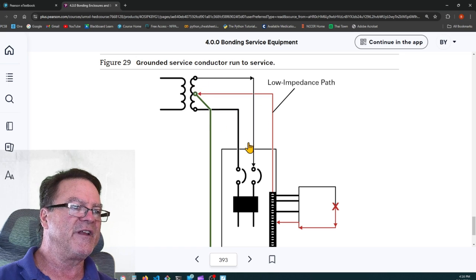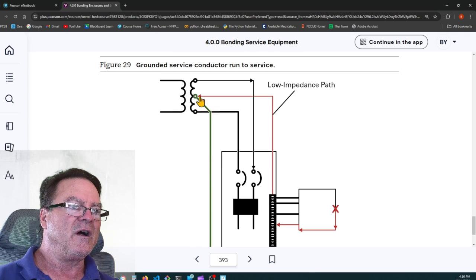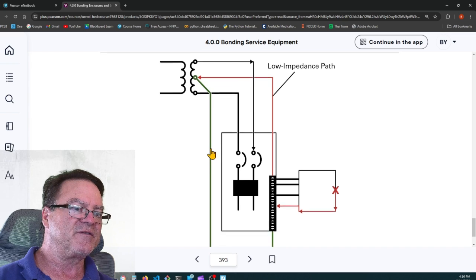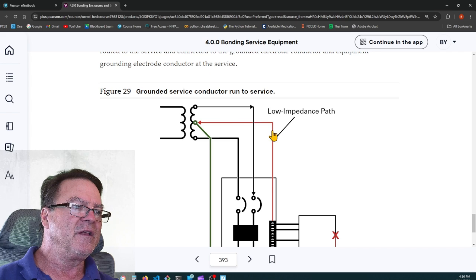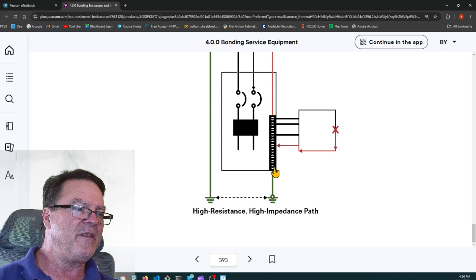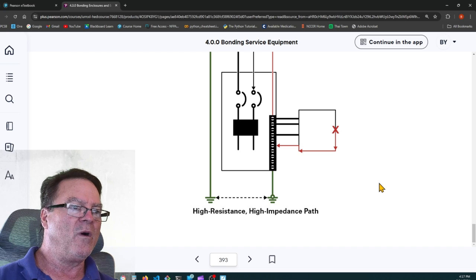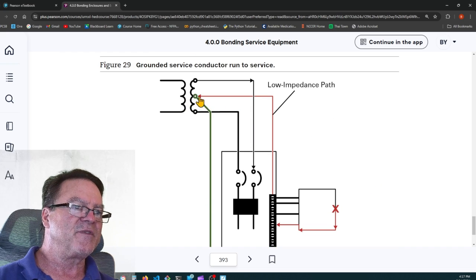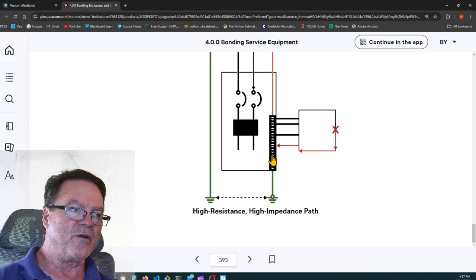So, here is the load side of a transformer feeding a panel. This is the main circuit breaker to the panel. And here is the ground from the center tap of the secondary of this transformer going to ground. Then we have the low impedance path. That's the neutral going to the neutral bar. And then this is also grounded. The neutral bar is also grounded. So this gives us a low impedance path. Actually, they're saying it's going through the earth. So it's a high resistance, high impedance path for this fault current. That's not good. What we want is a low impedance path. So that's what this one is. This is the low impedance path, this neutral going back to the load side transformer coil. That's the path that the fault current is going to take. It's not going to go through the earth. It's going to follow this neutral back to the transformer.